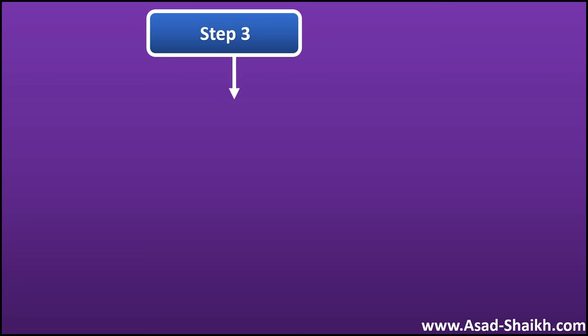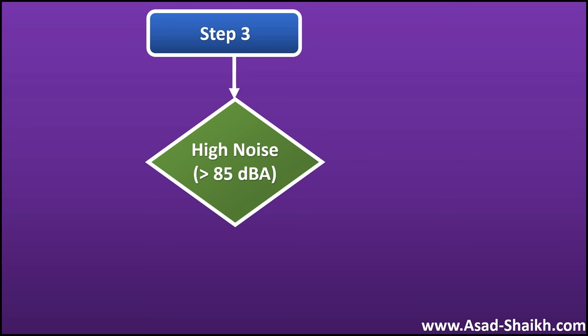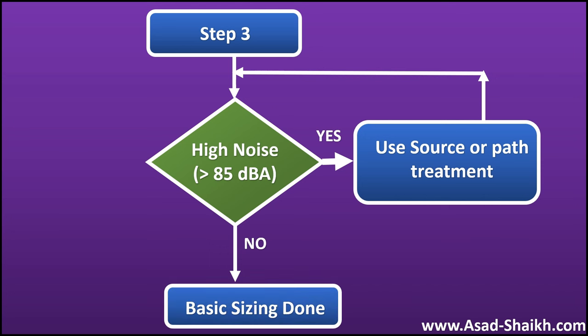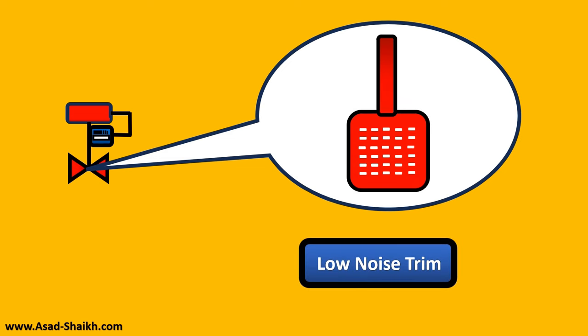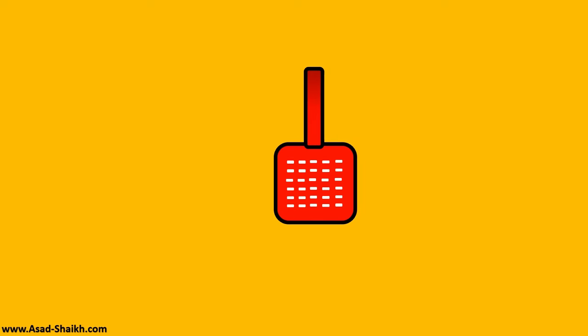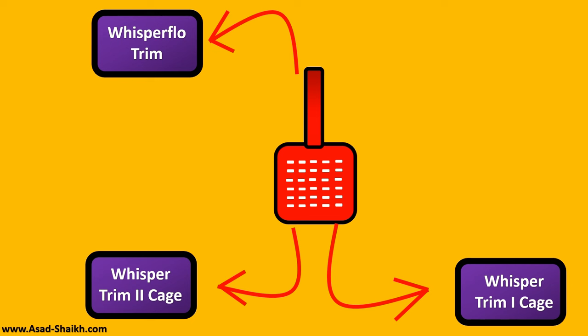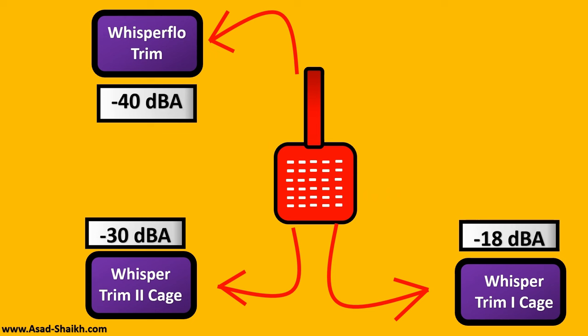Step 3 is to check for noise. Typically in projects the limit is 85 dBA, though it can be 90 or 80 dBA depending on project requirements. If noise is present, you apply source and path treatments and re-run the calculations. One important source treatment is the low-noise trim, which shifts the frequency so high that it won't damage hearing. For example, Fisher's Whisper trim series — Trim 1, Trim 2, and Whisper Flow — can reduce noise by 18 dBA, 30 dBA, and up to 40 dBA respectively, so you choose the trim based on how much noise reduction is needed.